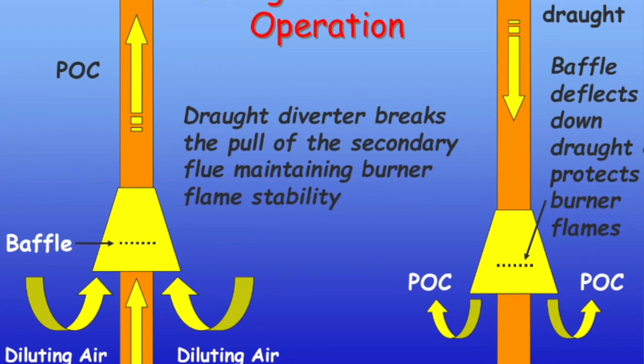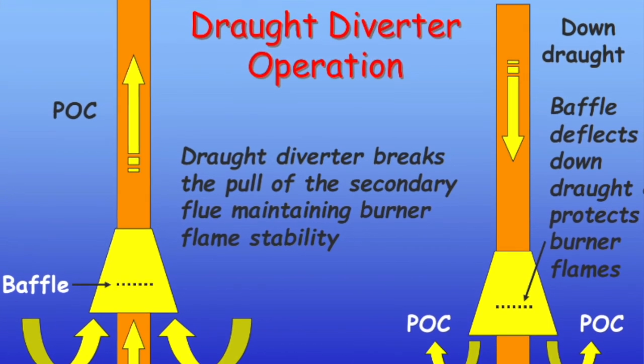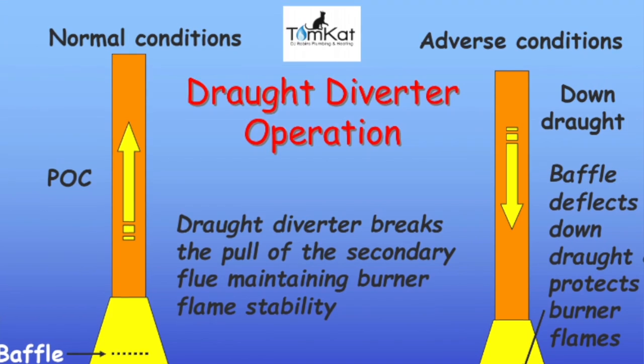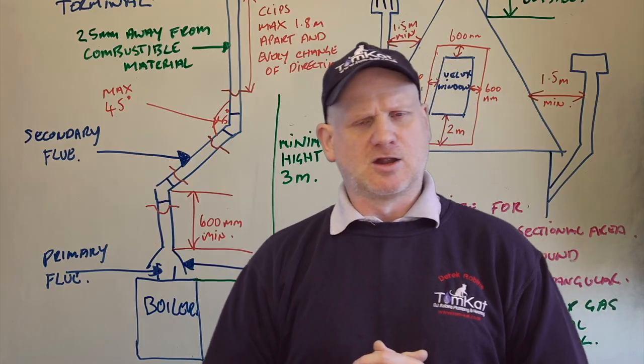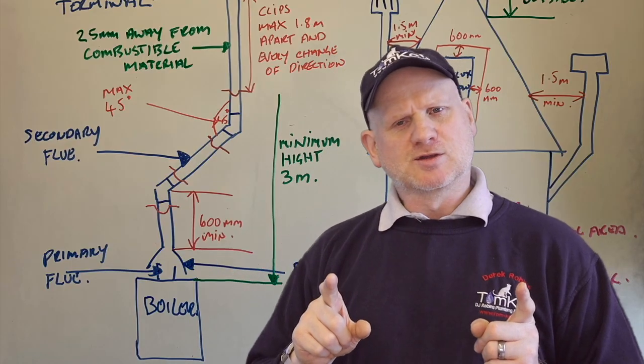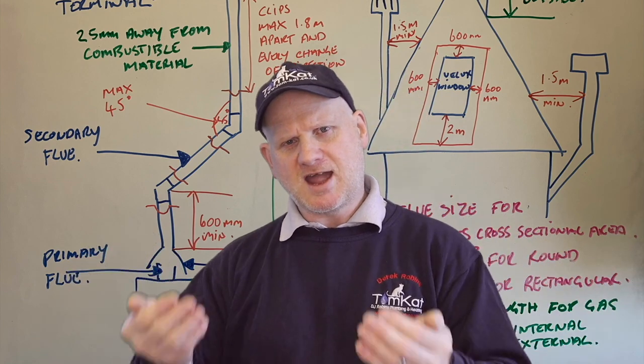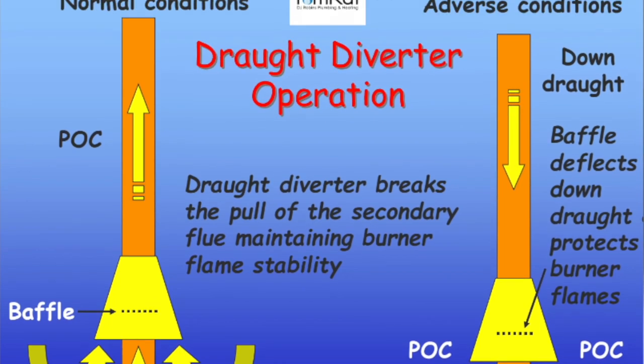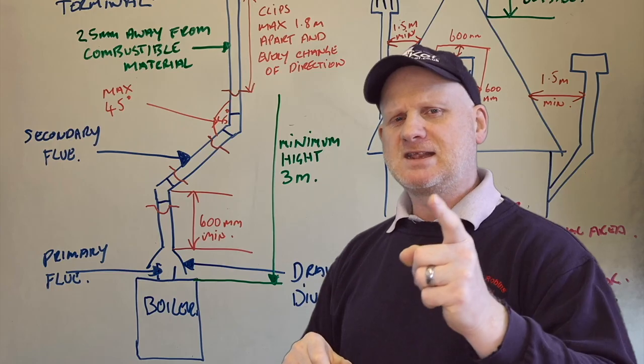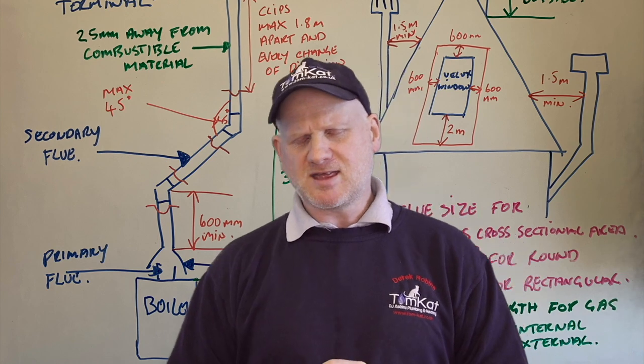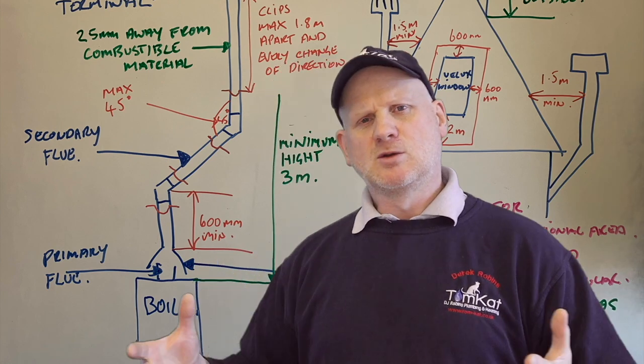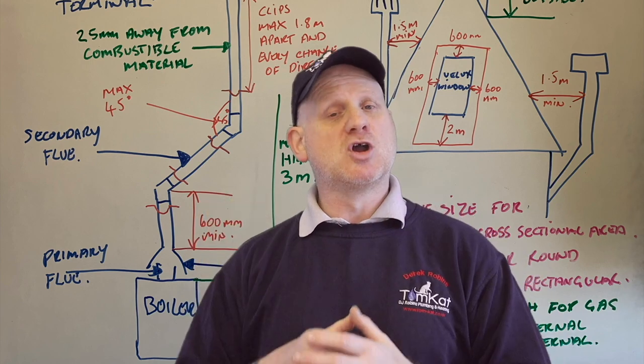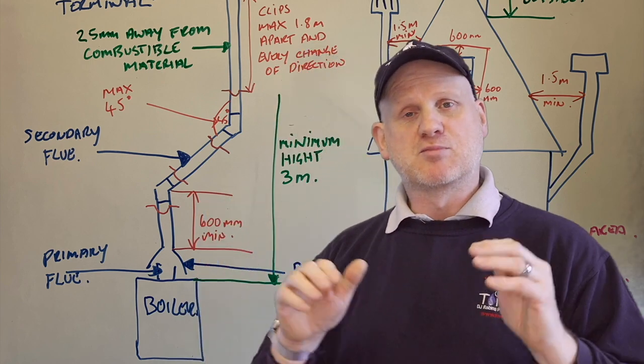First of all, if we get downdraft coming down the flue, it will push the products of combustion away from the burner so it doesn't affect the pilot or the burner. Also, it allows fresh air into the flue system as the boiler is running to dilute the products of combustion. And finally, it stops excessive flue pull — if the flue is pulling too much, it might lift off the burner and lift the pilot light.